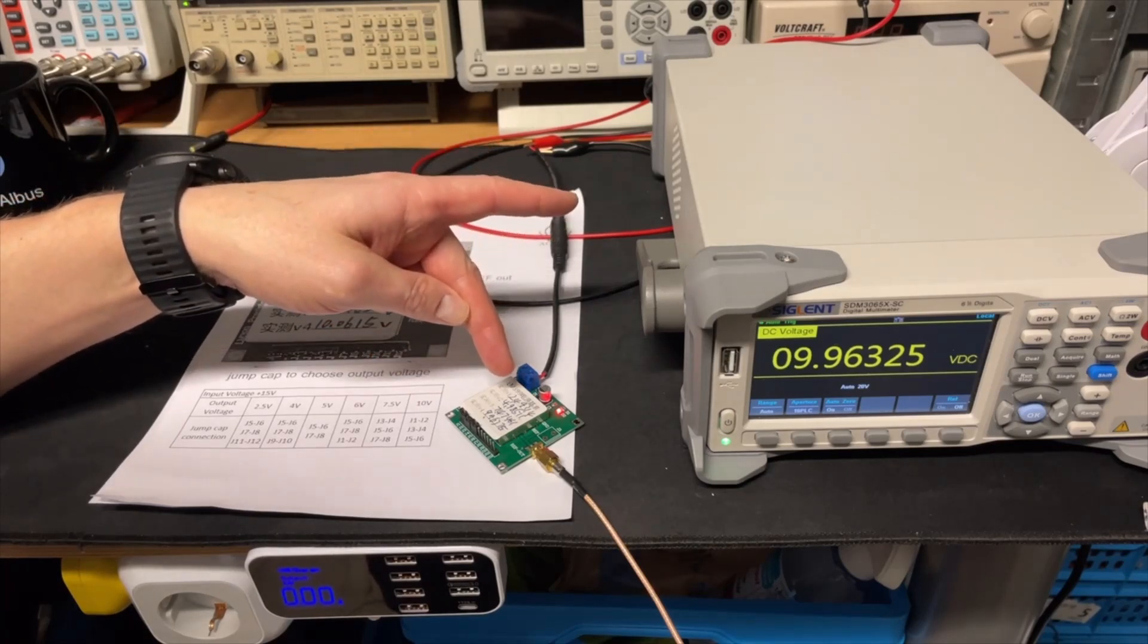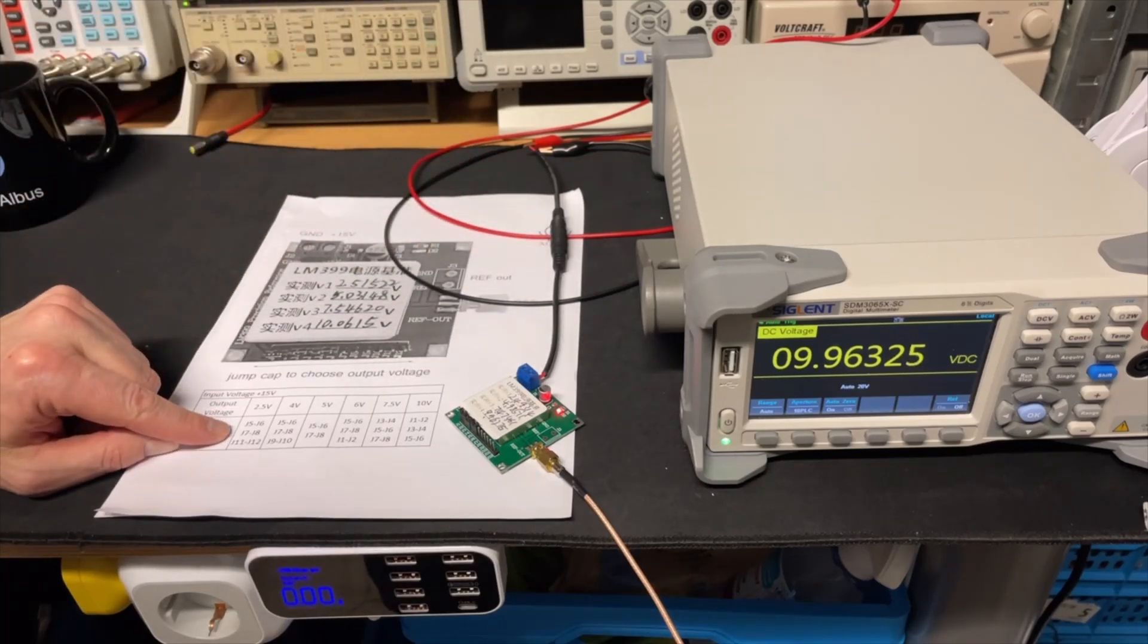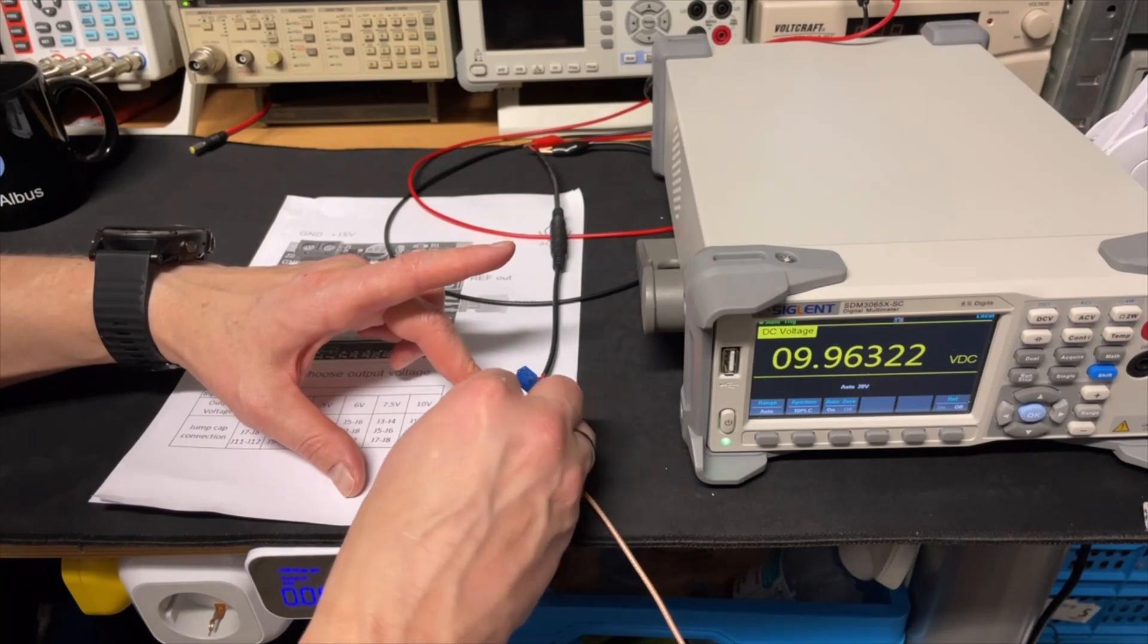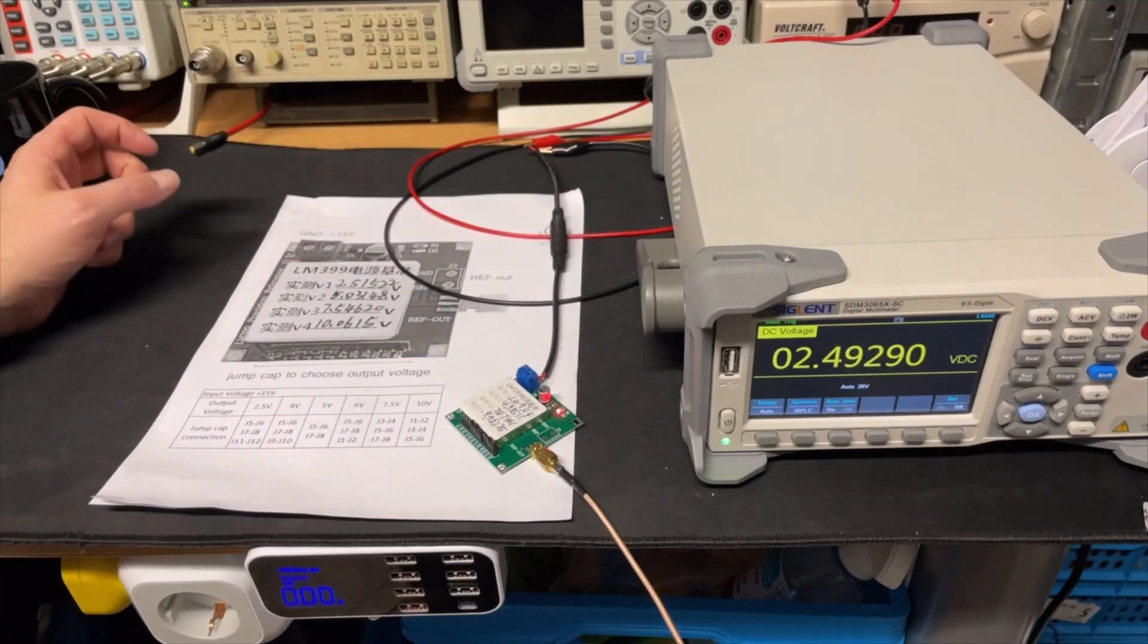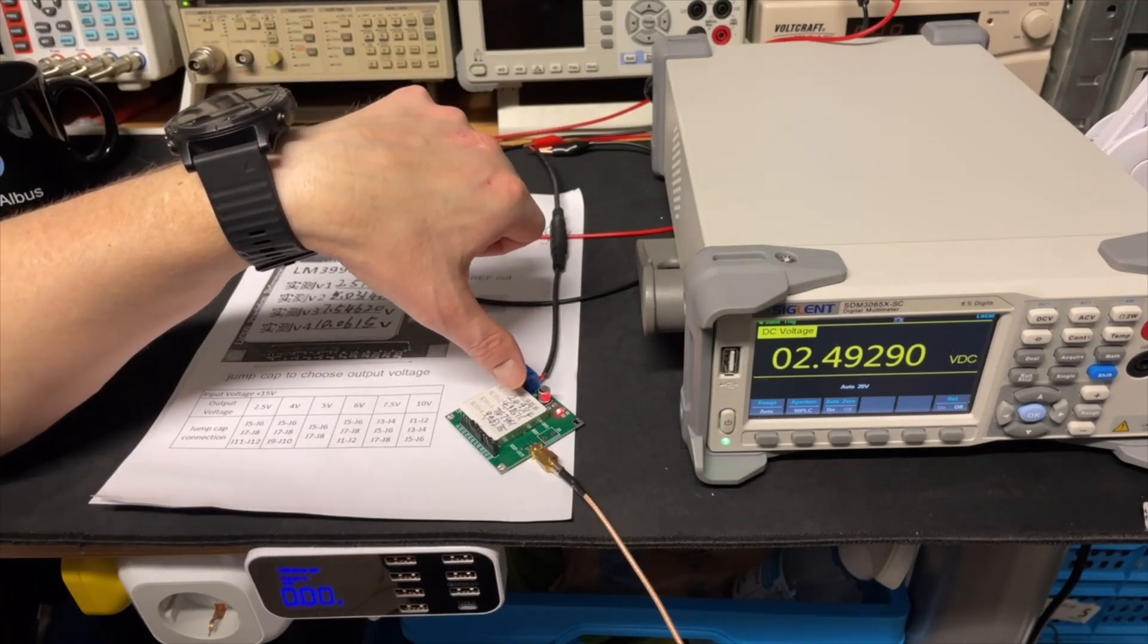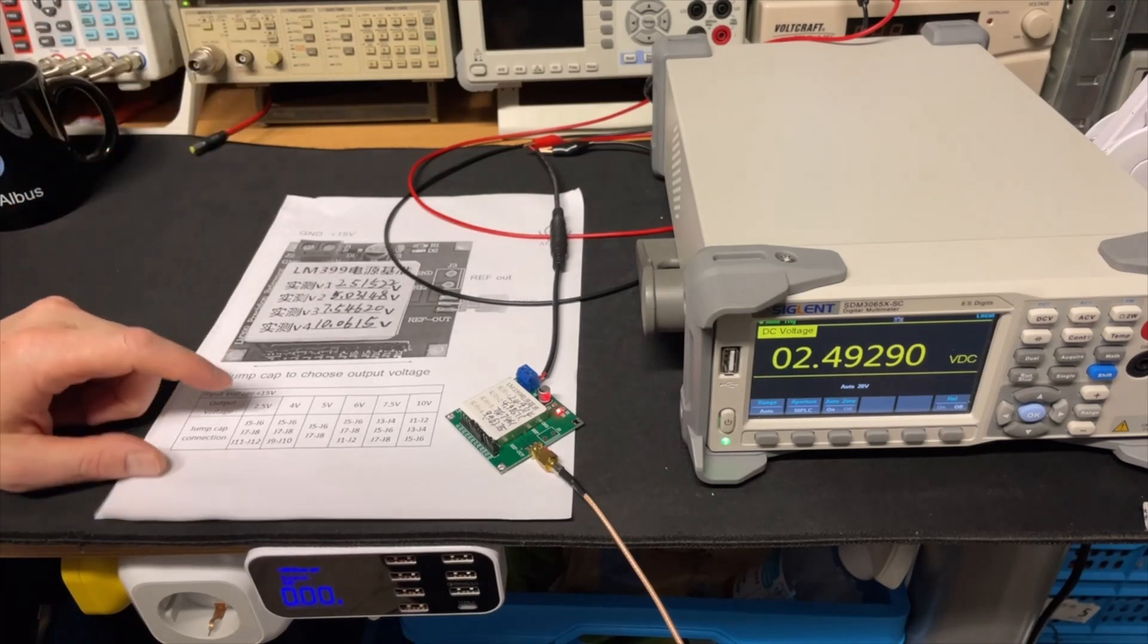We are now on the 10 volt setting, but they also say here they calibrated 2.5, 5, and 7.4. Let's try the 2.5, so we need to do the 5, 6, 7, and 8, and 11 and 12. This should be 2.5, it is. They say they calibrated at 2.5 that it should be 2.49314, so it is a little bit low. I don't know how they did that because the 10 was spot on.